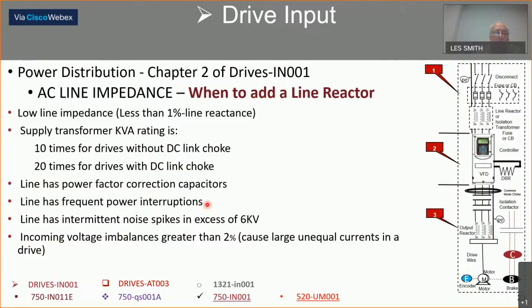Line has frequent power interruptions. It's at the far point of the plant, the last one on the road, where you have a lot of interruptions. Or we have intermittent noise spikes. Say you've got a 100, 200, 300 horsepower motor on a starter that is picked up and dropped out. You may have an inductive spike coming back. We put the reactor in there. Incoming voltage imbalance greater than 2%. The reactor fights the urge to change. If the voltage goes up or the voltage goes down for milliseconds, that reactor will hold that energy.